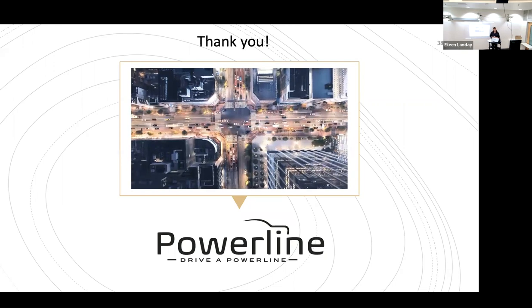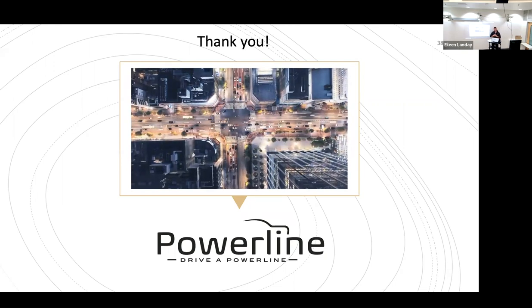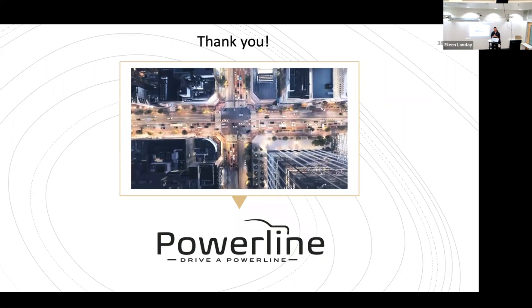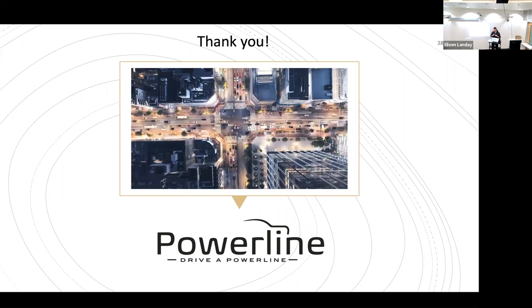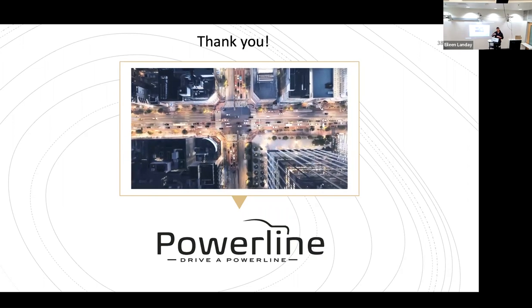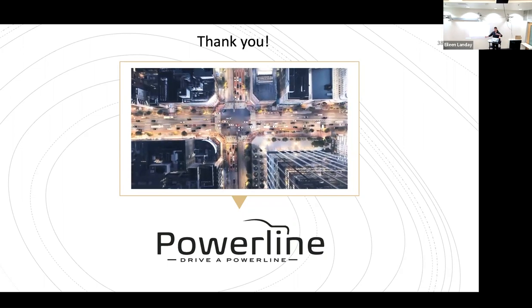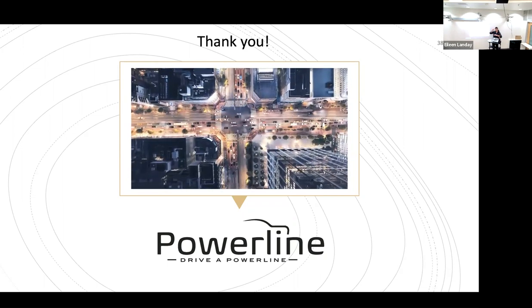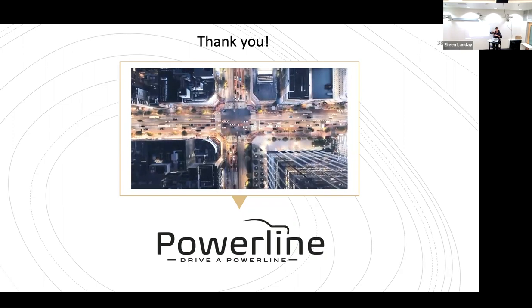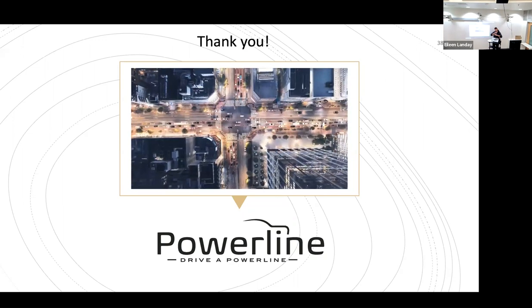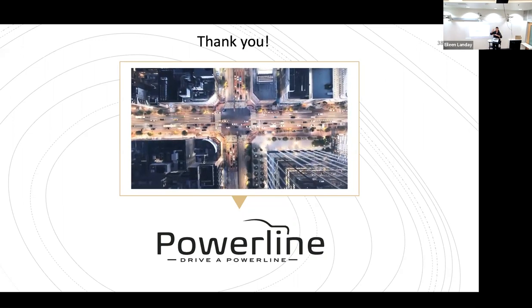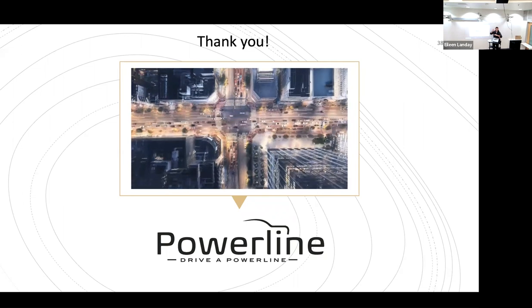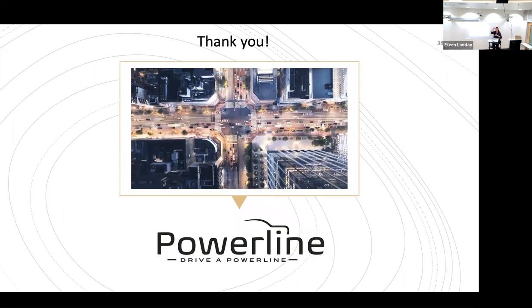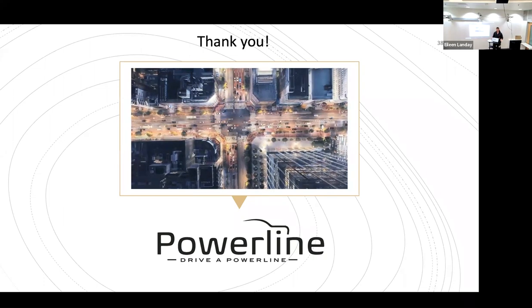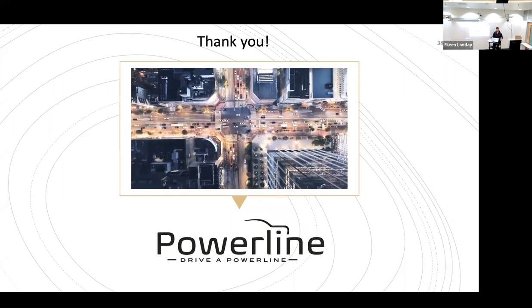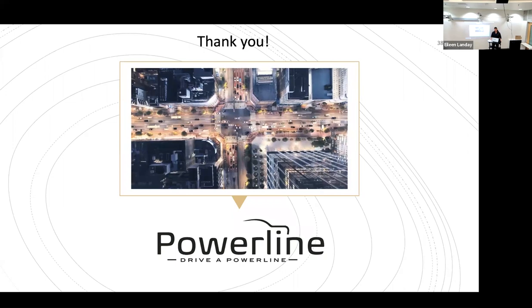Value stacking is actually really easy with a battery. For the most part, as long as you have sufficient capacity to ramp up to provide an additional service, you can provide both and stack them. For example, suppose you have a 100 megawatt battery, 50 megawatts is energy, and you have another 50 megawatts. You could do 25 megawatts of reg up, following a signal, with your baseline starting at 50 instead of zero. Then if you do another 25 megawatts of contingency capacity, as long as you're able to increase your capacity or generation during times you're needed, that works. Does that make sense? So you can stack up to your full power capacity in a lot of markets.